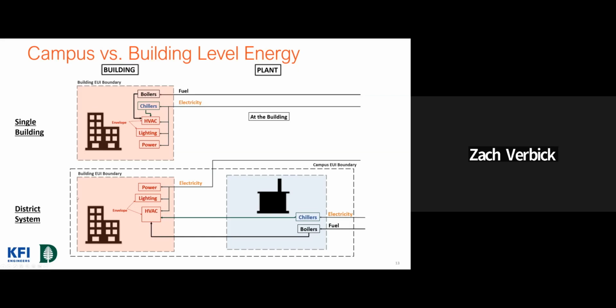When you go down to a district system, the way building EUI is calculated, it's still everything within the red box. But what we're seeing now is only the chilled water energy coming in, the hot water steam energy coming in, and the electricity coming in. So in a traditional system, this will actually show a more favorable building EUI than a single building, because it's not accounting for distribution inefficiencies or inefficiencies in the plant.